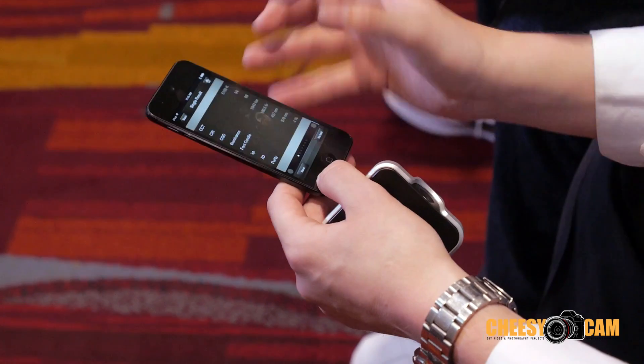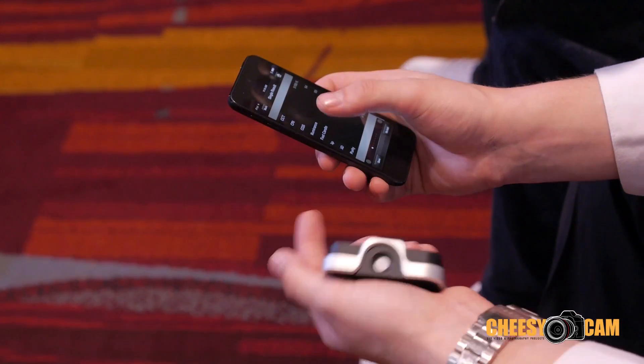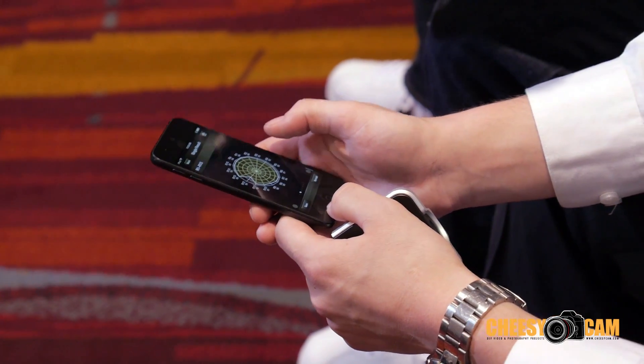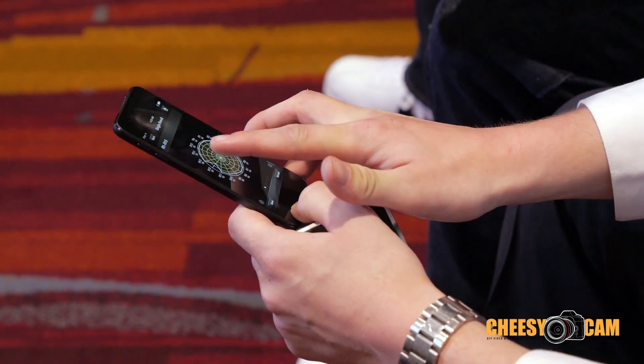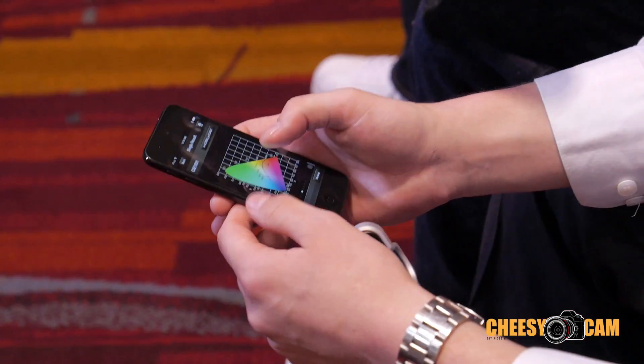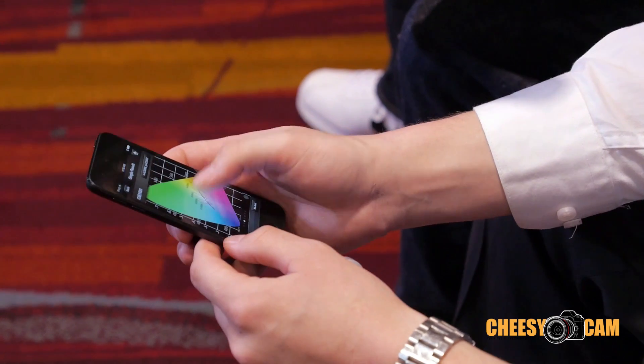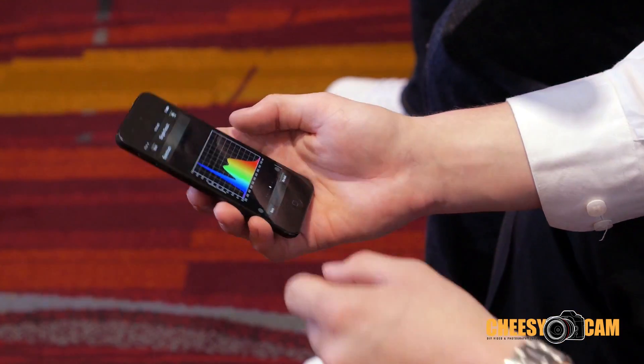Obviously it's not 100% on the dot, but it has a good error margin. You can see all the luminance, foot candle, and CRI readings. You can slide through — it shows the R chart, R1 to R15. R12 is slightly negative but in general it's a really good, full light. You can also see the CIE 1931 and 1976 chromaticity diagrams, and when you see the full spectrum, every parameter you selected has a chart.